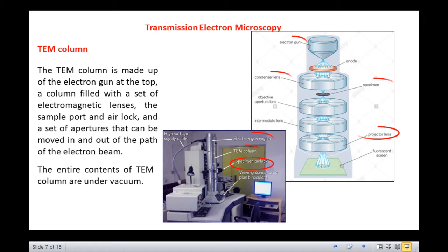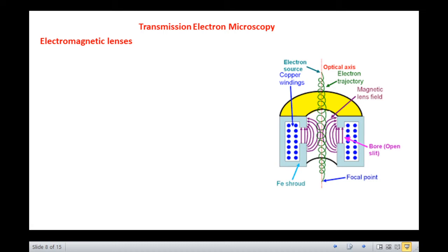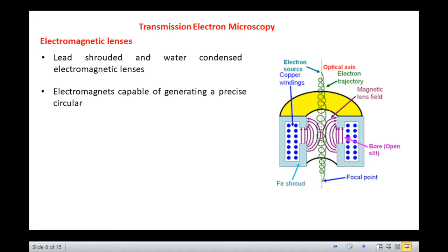Let us now discuss about the electromagnetic lenses, a major component of the transmission electron microscope. A series of lead shrouded and water condensed lenses are present in the TEM column as we saw in the previous slide. These lenses are electromagnets capable of generating a precise circular magnetic field.